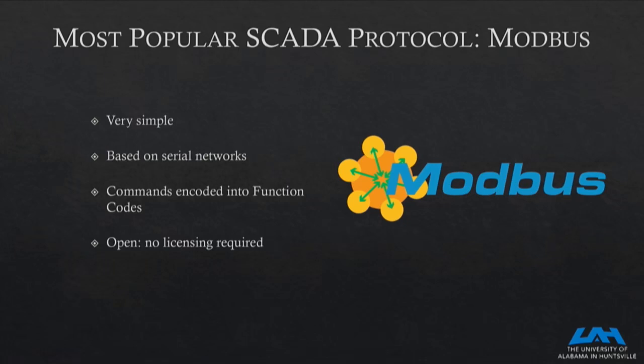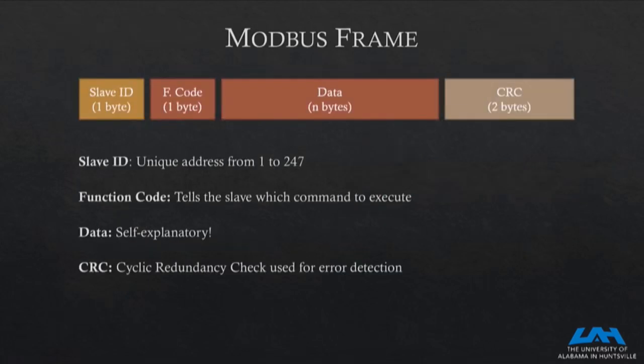The commands for the protocol are encoded into function codes, so you have different function codes for different things you want to do. It's open, which is probably why everybody supports Modbus, since it doesn't require any licensing. You can pay the Modbus Foundation to have your device certified to make sure it follows the full standard, but you don't have to do that to support the protocol, there's no licensing fee. This is the Modbus frame, what it looks like: the first byte is a slave ID.